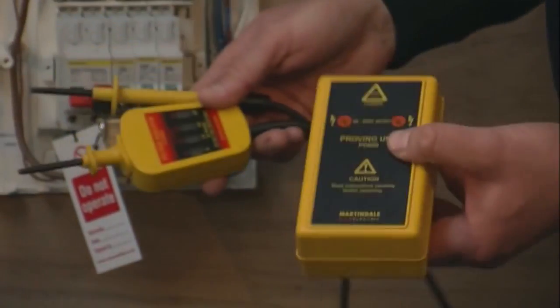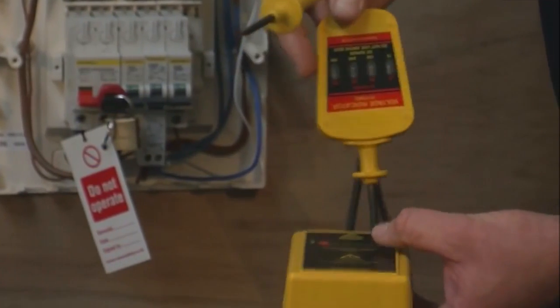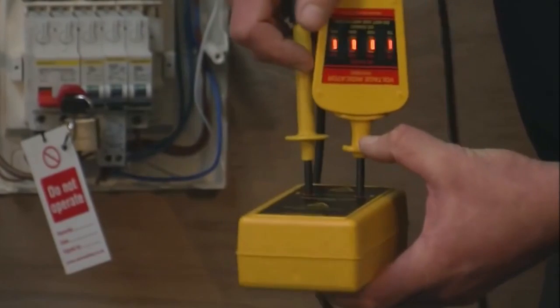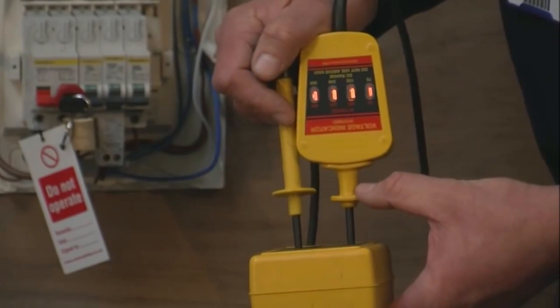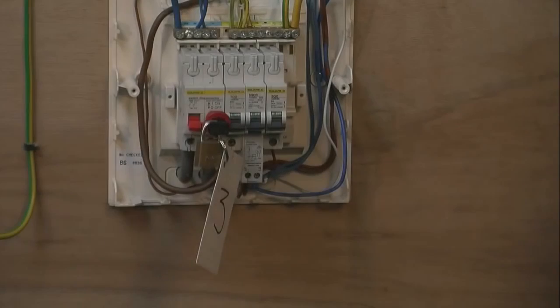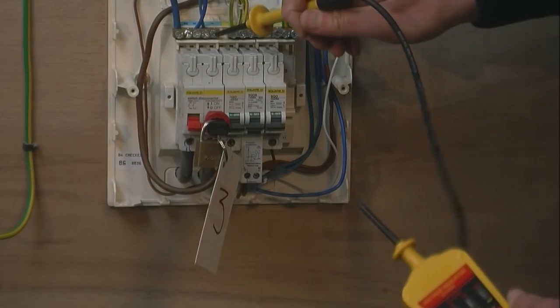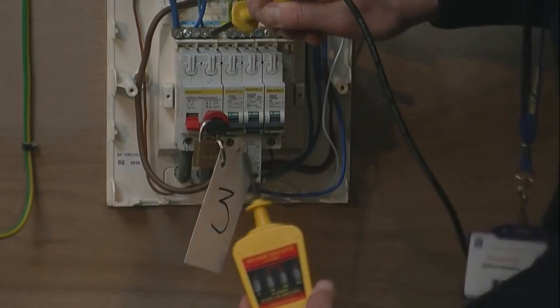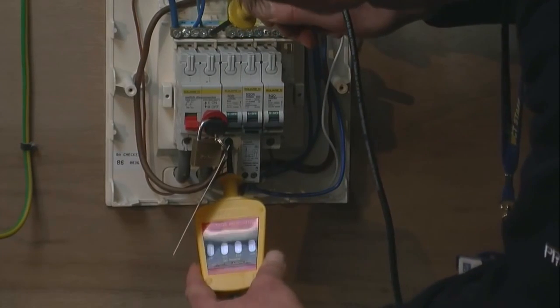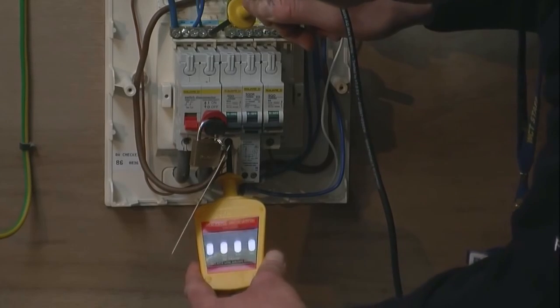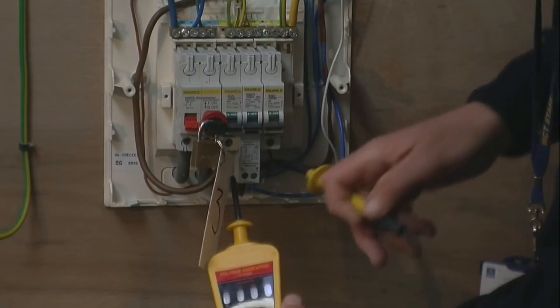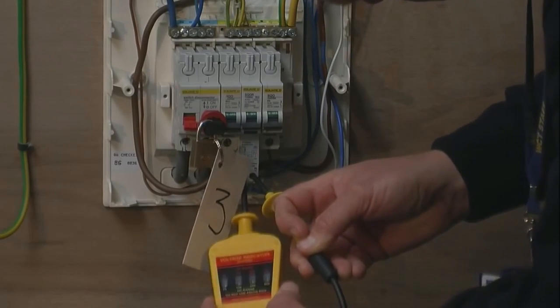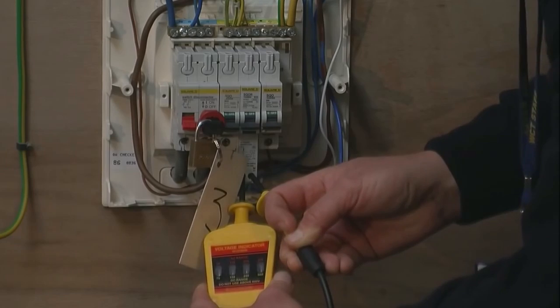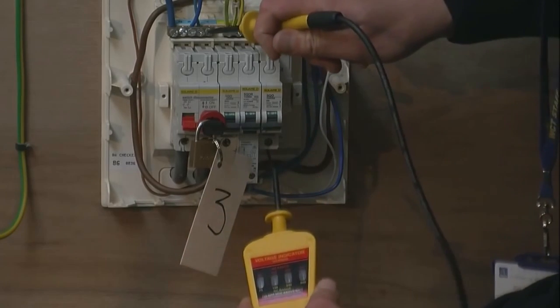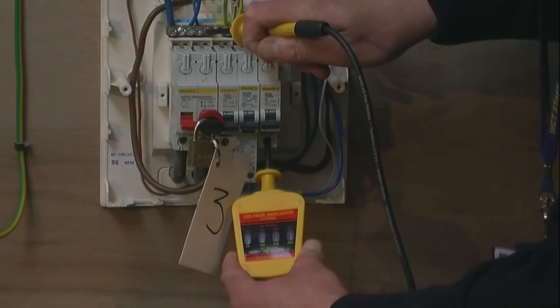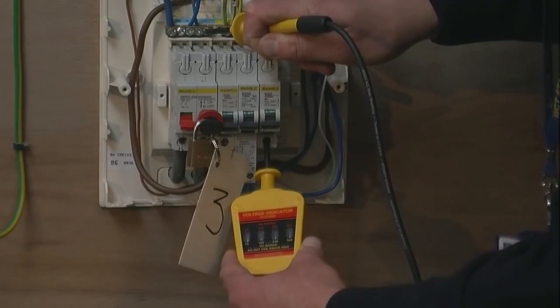This is the voltage indicator and this is the proving unit. We insert the voltage indicator into the proving unit, and as you see, all the lights display on the voltage indicator. Having removed the fuse board cover, we now place the probe onto the neutral bar and then onto each of the circuit breakers. As you can see, the next circuit breaker along is an RCBO, so we go onto the neutral and the line there, and as you can see, the lights are not lit. We then go back onto the neutral bar there and then onto the final circuit.